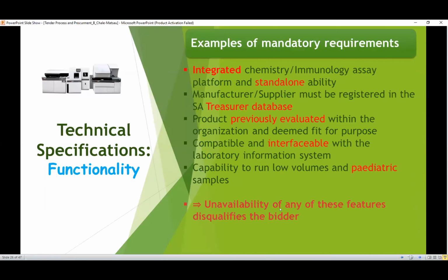I just want to now talk about the technical specifications. The first one will be the mandatory. Similar to what we have said with regard to the administration, this is the functionality of the equipment itself. So for example, in our case, we would like to have an equipment that has the integrated chemistry and immunology assay. But you also would like to have a standalone ability. In other words, if the one component doesn't work, it should not interfere with the other. So if we have a problem on the chemistry side, immunology should still be working. If the supplier doesn't have that, that is a problem.